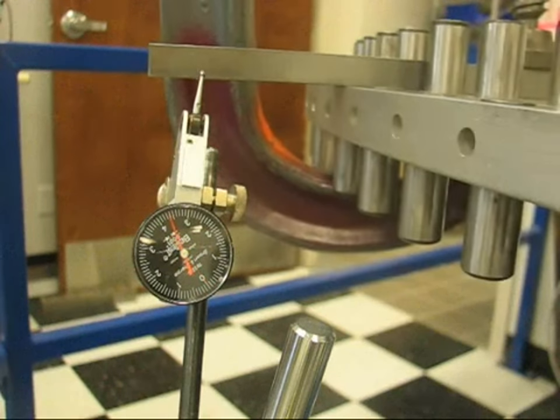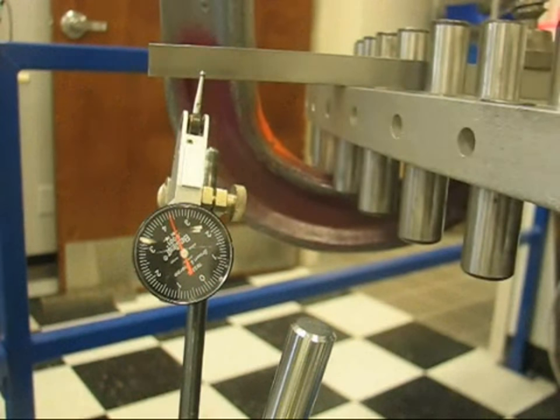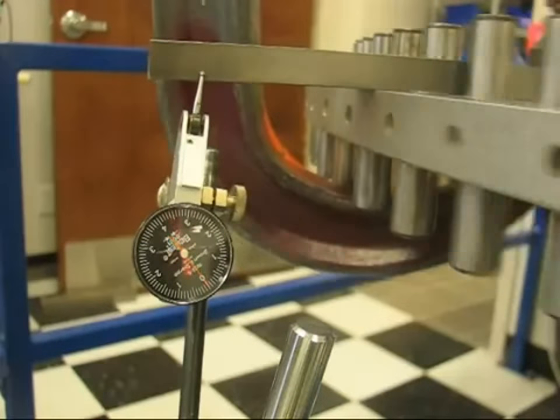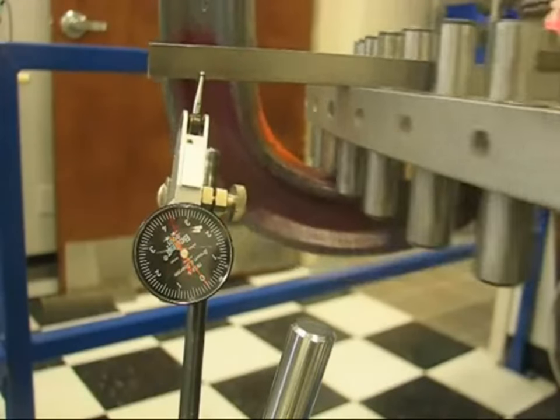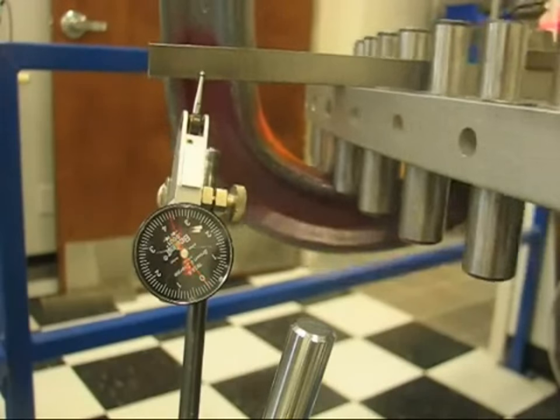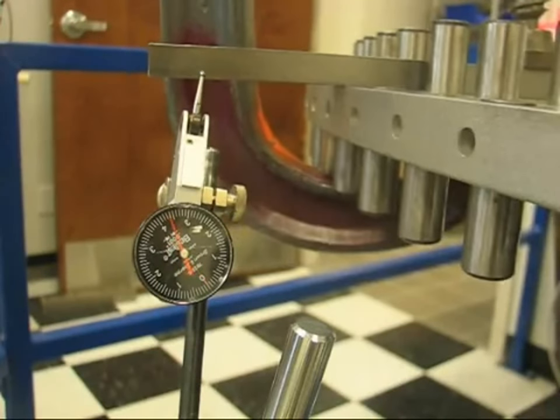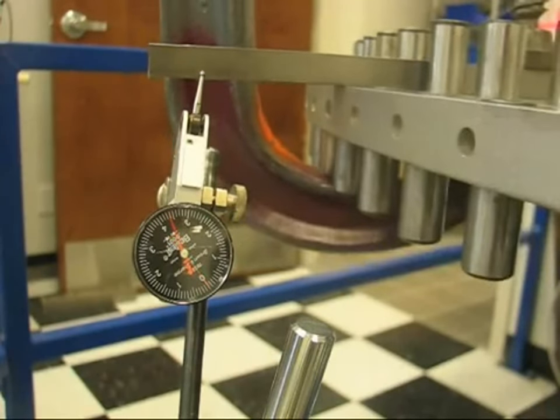The motor is now commanded to move away from the zero position and then return to the zero position. As you can see, on successive moves, the motor returns to zero with a variance less than one ten thousandth of an inch. Keep in mind that this is on a twenty-seven inch radius from the center.